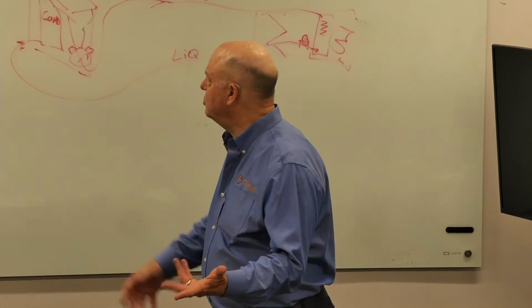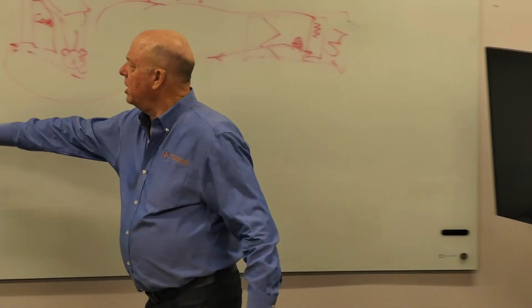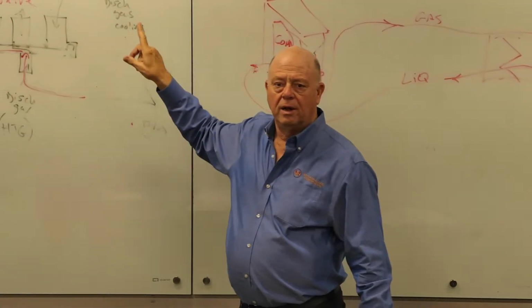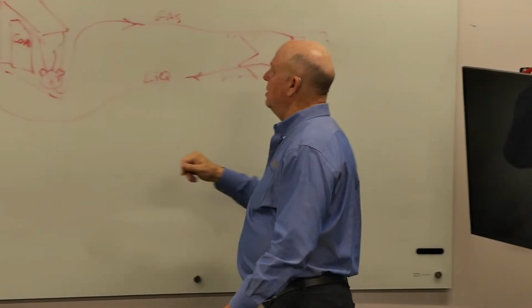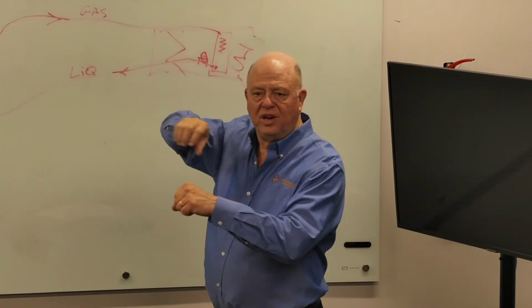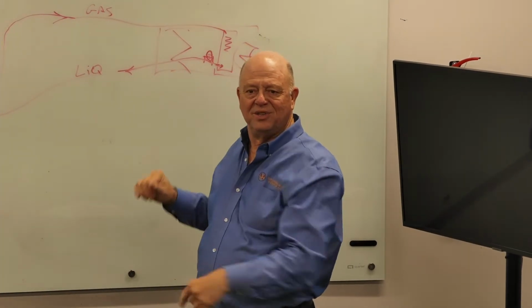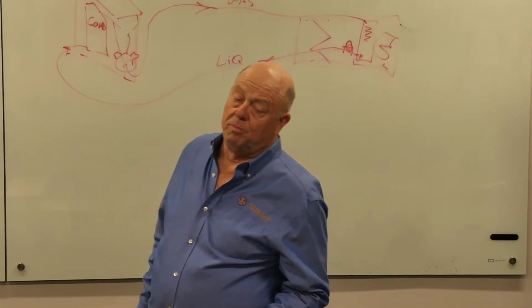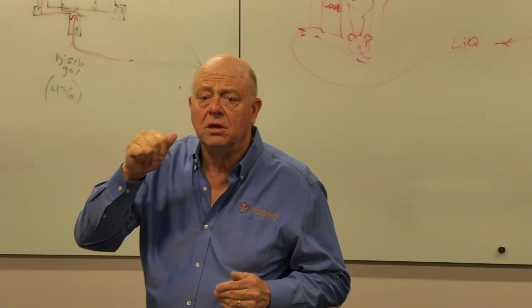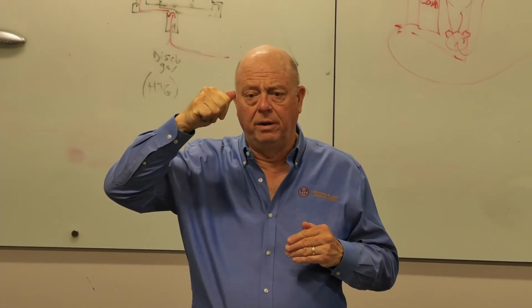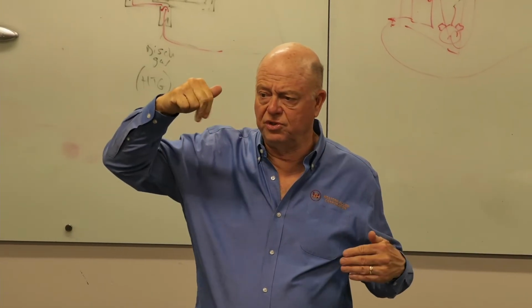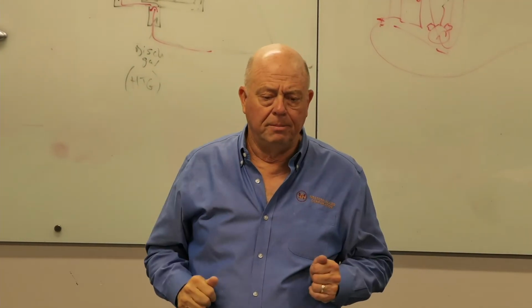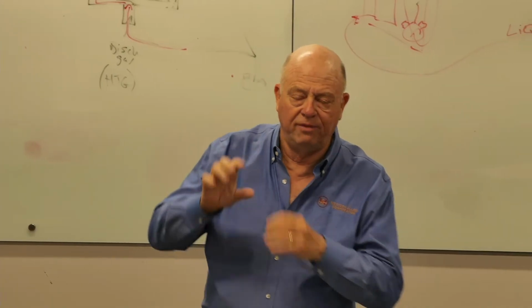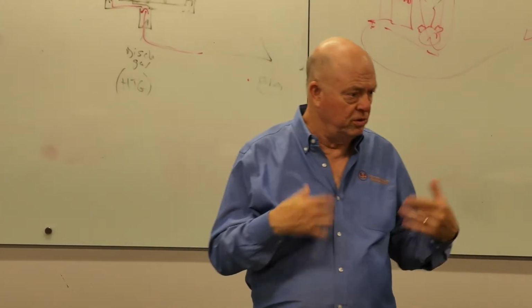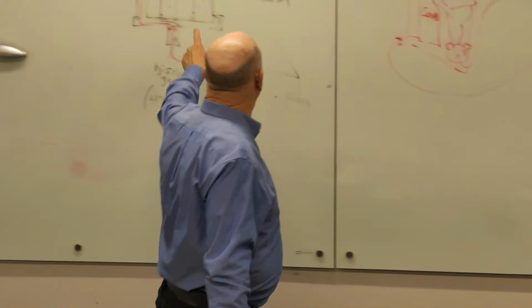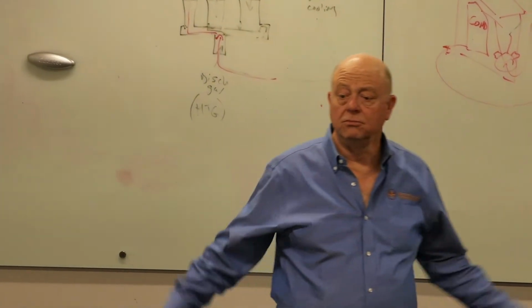I guess I should just mention, remember we were talking you can split and go either way? And remember we were talking, well, you'd need a different TXV now because the refrigerant's going different ways and this and that. What you end up with is a bunch of check valves. So the refrigerant can only go one way. In cheap little residential systems, that's what you got. In commercial systems, we might have to put in solenoid valves, we might have to do some other things. But the heart of it is what's going on here. Anything else?